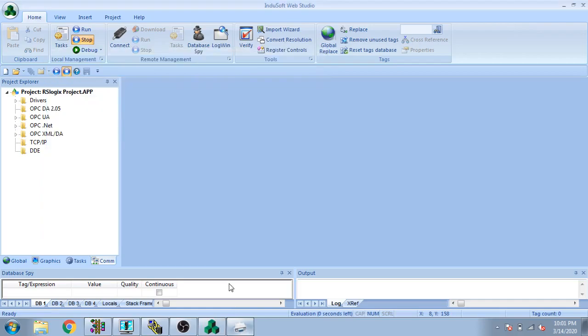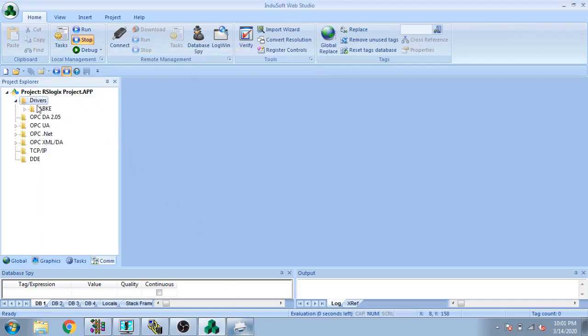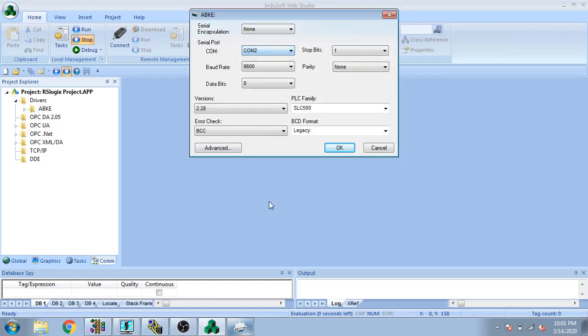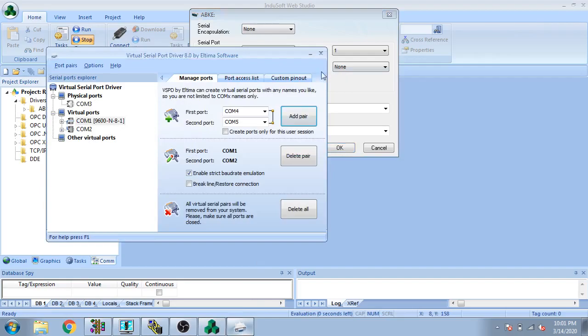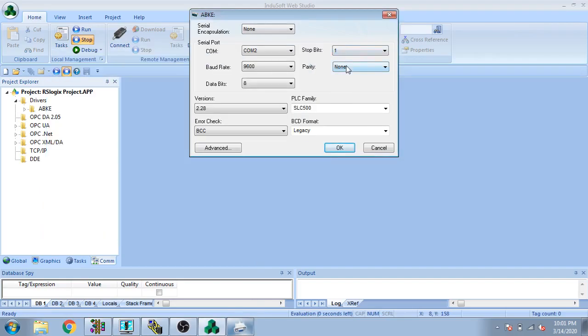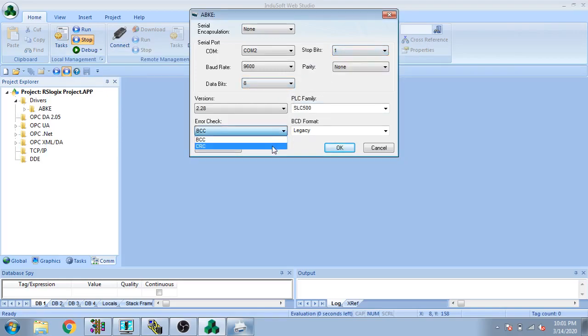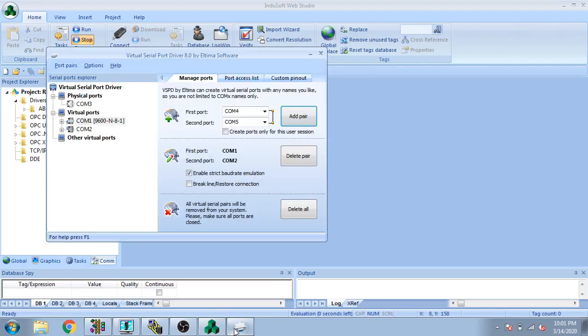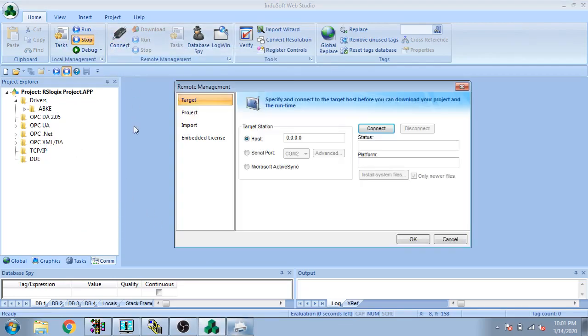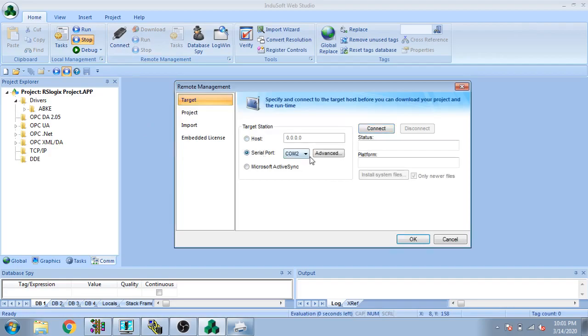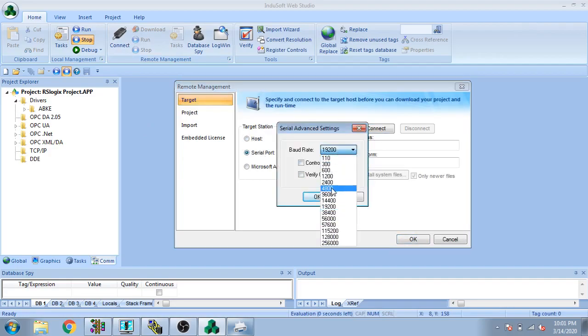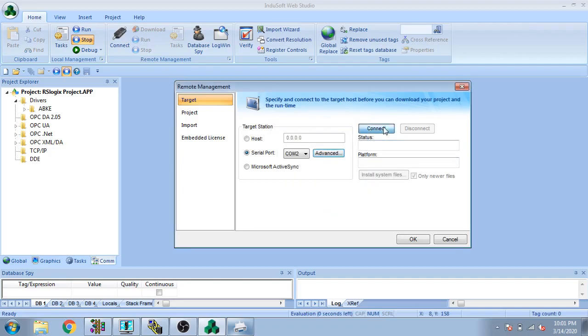I need to configure the settings: select COM port 2 because we are using a crossover, parity is None, data bits 8, stop bits 1, and BCC selected. I also select SLC 500 as the device type. Then I go to connect, set 9600 baud, and click Connect.